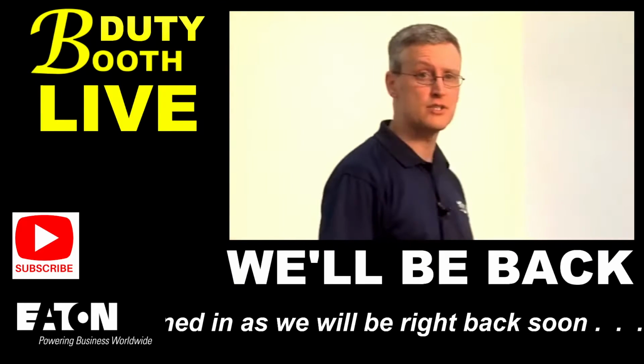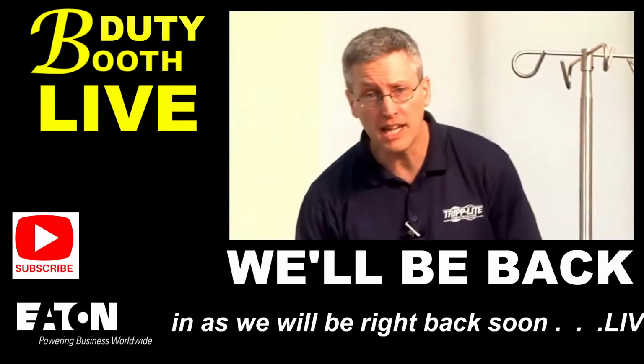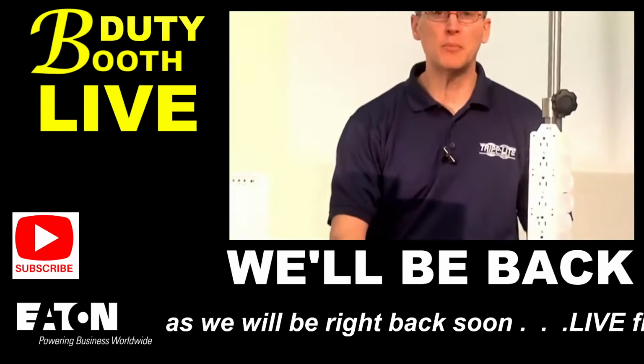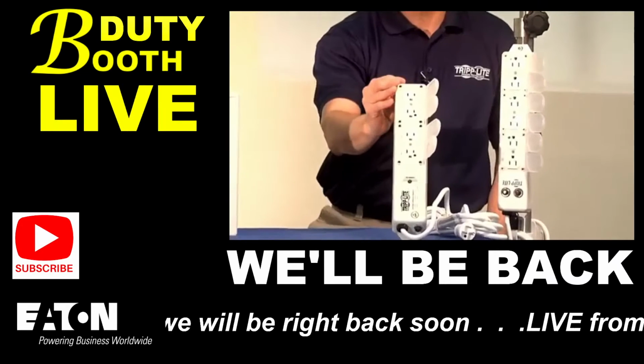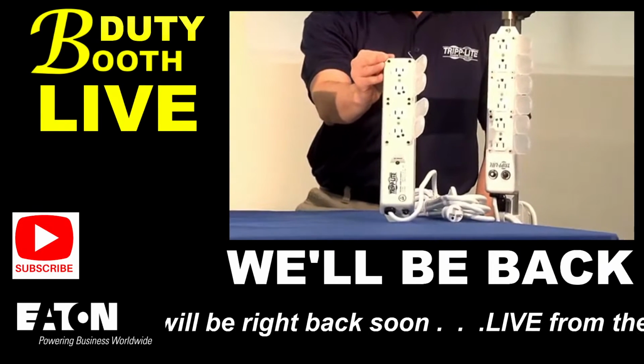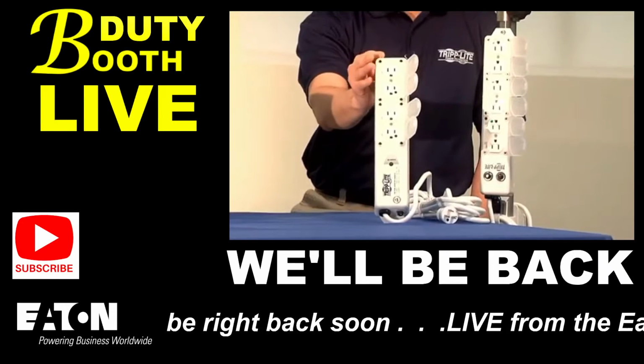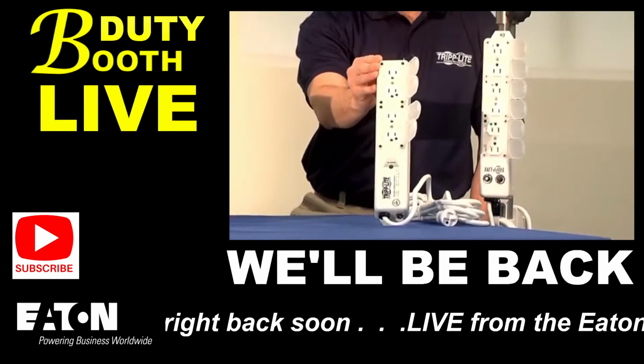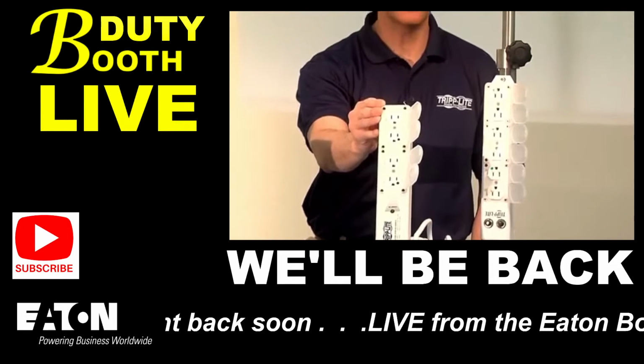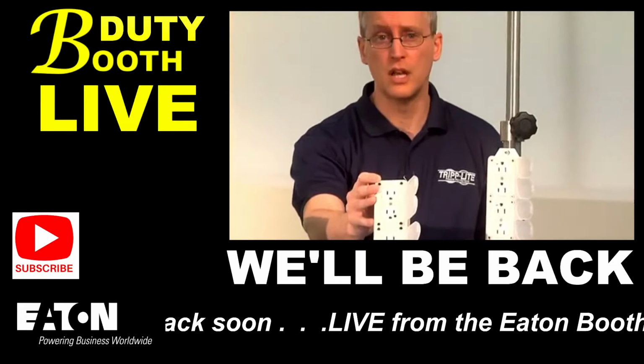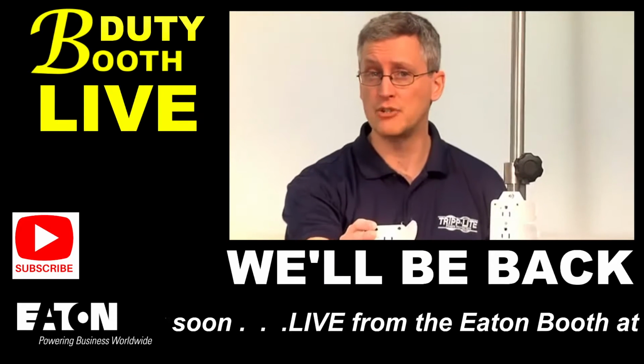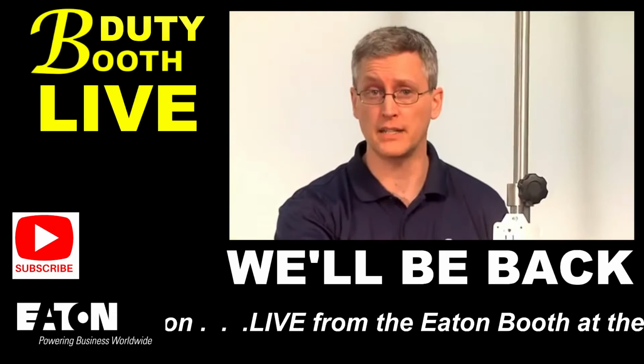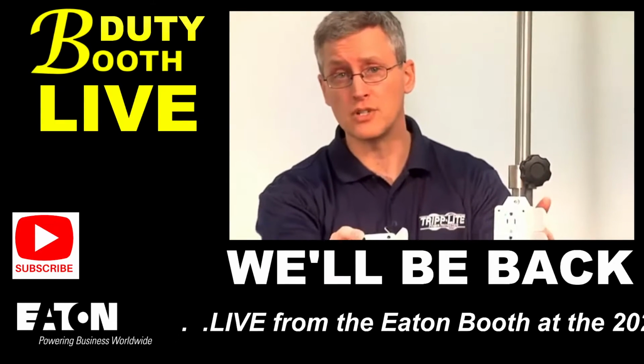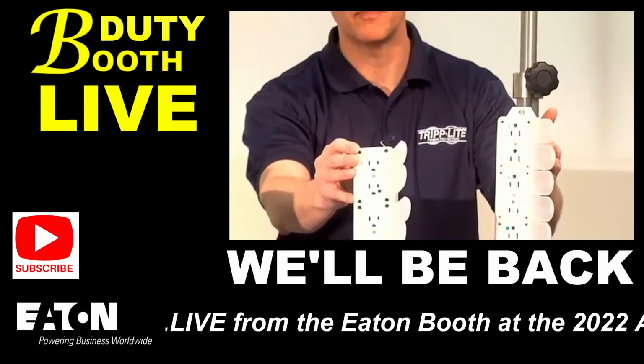If your customer simply wants to add additional outlets while still maintaining compliance, sell them a Tripp Lite medical grade power strip. This product distributes power but doesn't include any power protection. Unlike UPS systems and isolation transformers, power strips do not have to reduce leakage current to remain compliant. Here is a mounted version of the power strip.